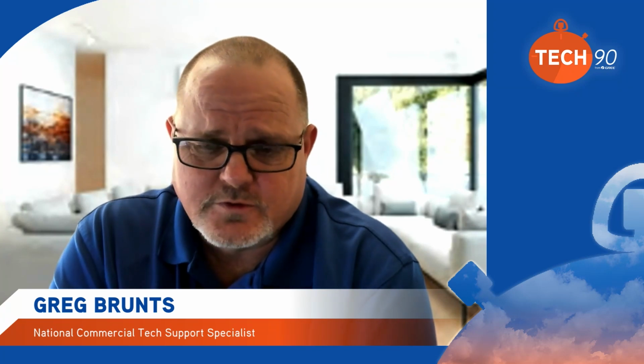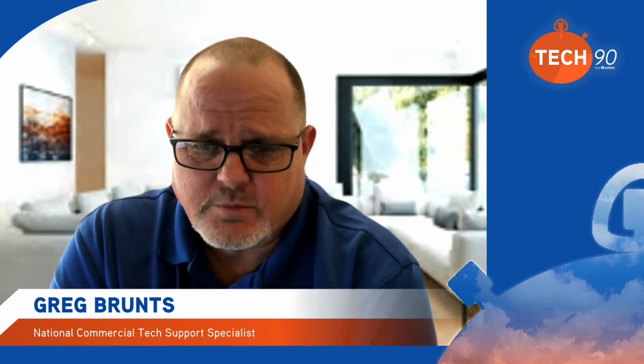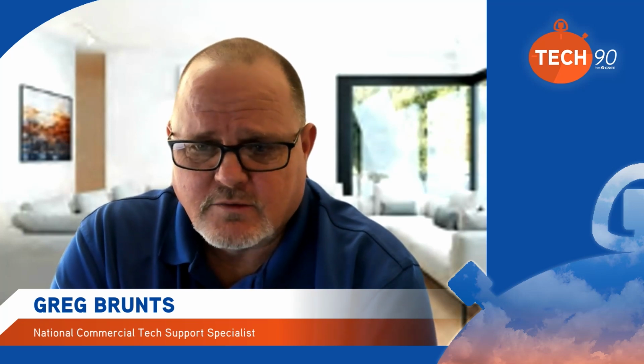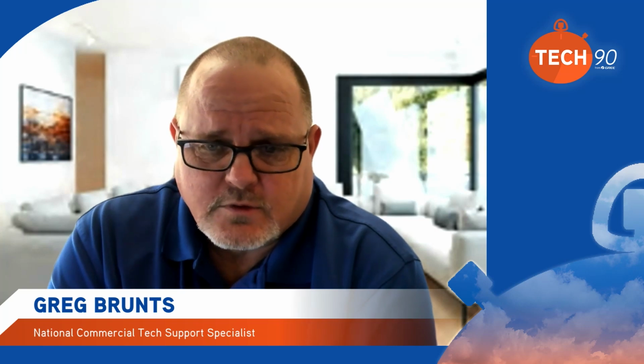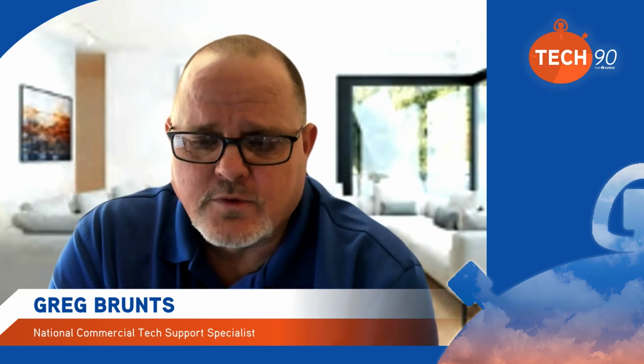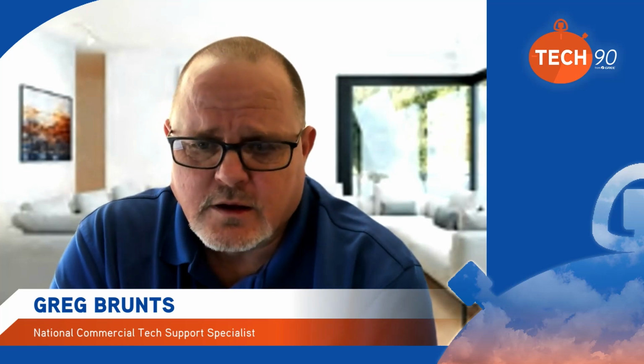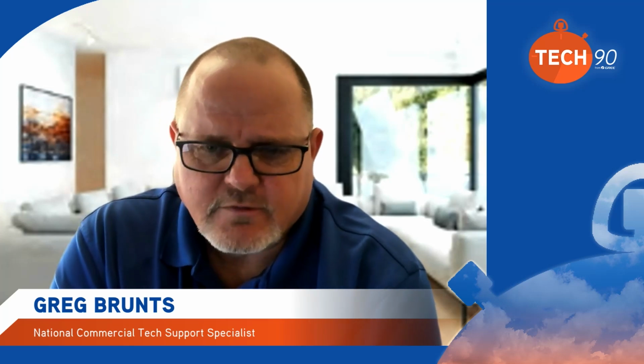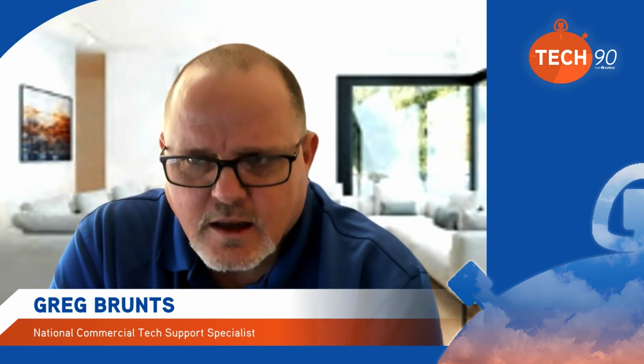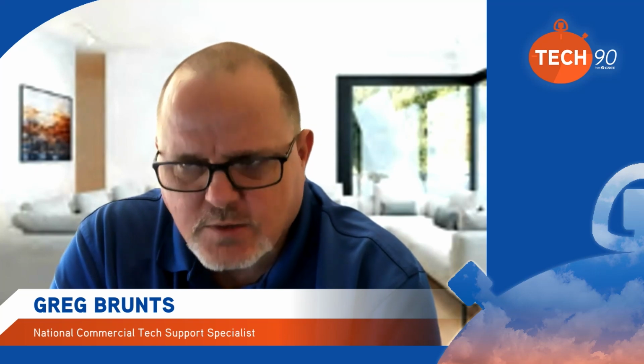I go back 20 years ago when I was still in the field. I had those conversations with consumers constantly, because the big thing was having a programmable thermostat and having setback. People would want to, in cooling mode, because it's essentially the same thing, do like a 10-degree setback because they're at work all day. Well, I'm like, okay, when you walk in the door at 5 o'clock, right in the heat of the day, you're telling this machine to catch up 10 degrees. Just like you're saying, that thing's going to run for 2 hours plus to catch back up. And chances are you wouldn't have had two hours of runtime the entire day, and that's just maintaining the temperature.